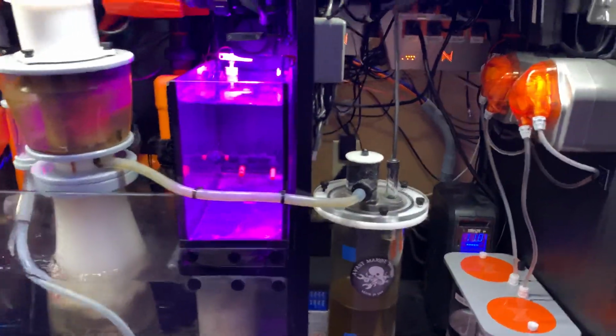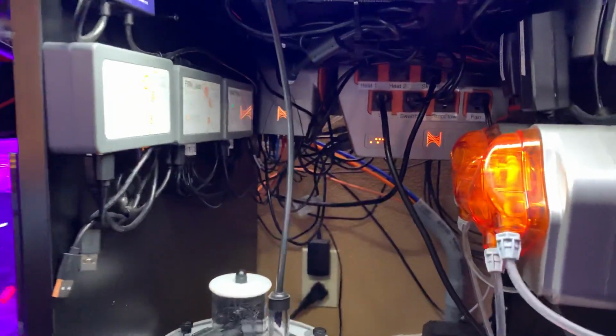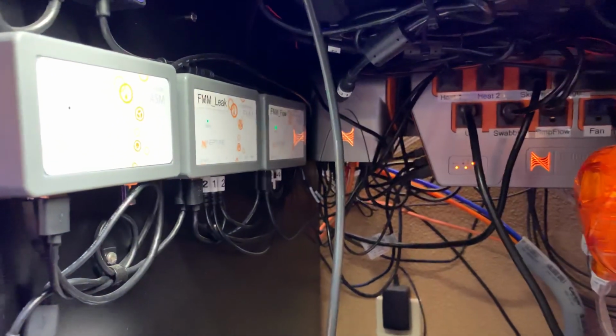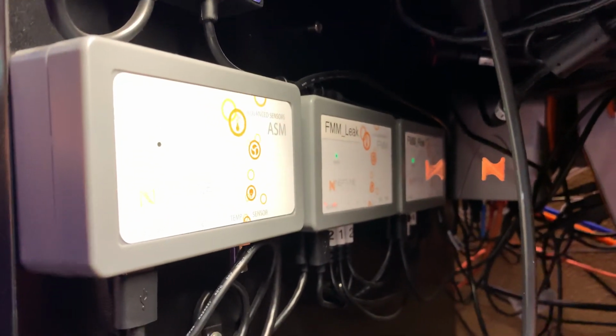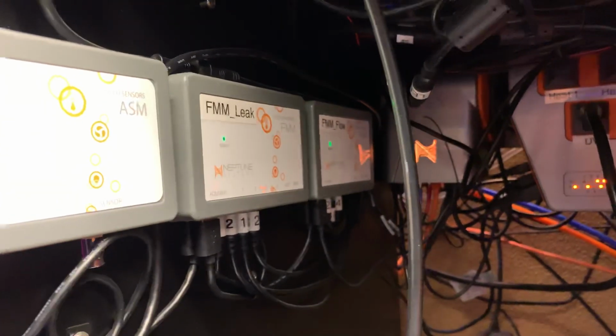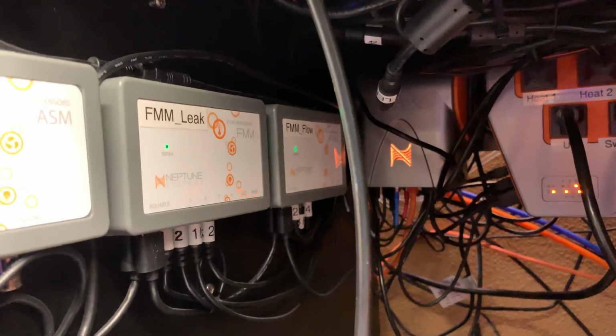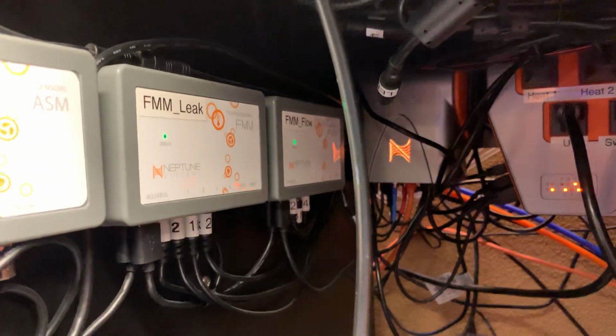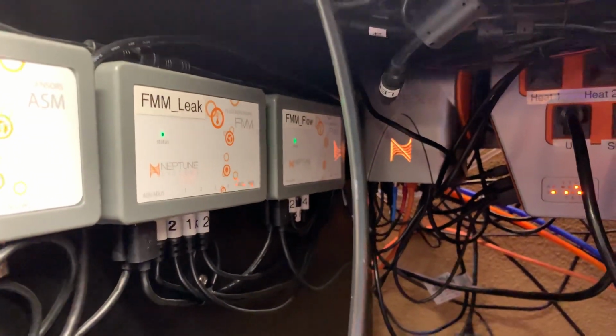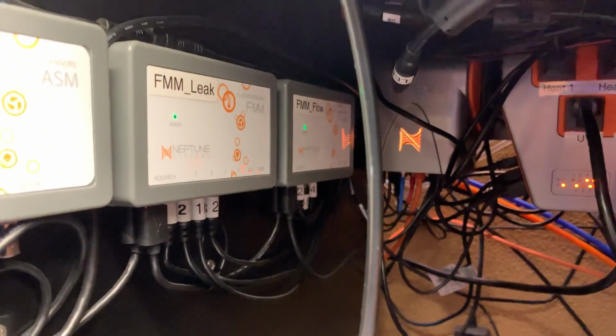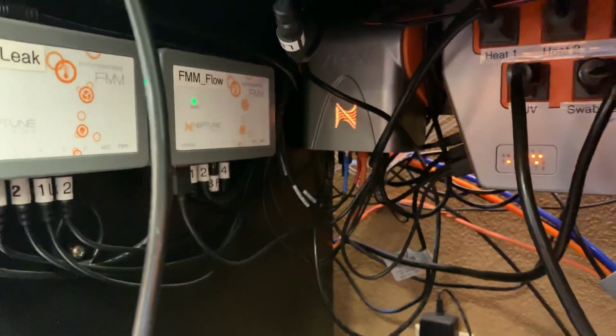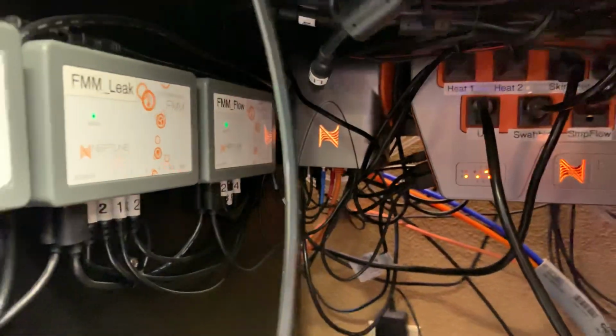On the control side, I have a Neptune Apex 2016 model with several modules. I have the ASM for the power monitoring kit, a couple of FMM modules, one for leak sensors and optical sensors for water levels, and the other one is dedicated to my 4 flow sensors.